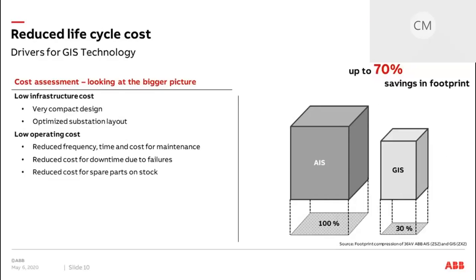In addition, when we use SF6 for isolation, the gas has a very unique property. It insulates 3 times better than air, which means that we can move the 3 phases closer together, resulting in a very compact switchgear design. This is proportional to the rated voltage. So at 36 or 38 kV, you can have up to 70% footprint savings when using GIS. This also results in a much smaller substation layout.